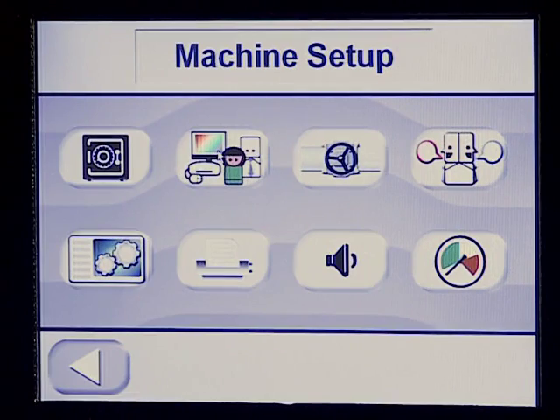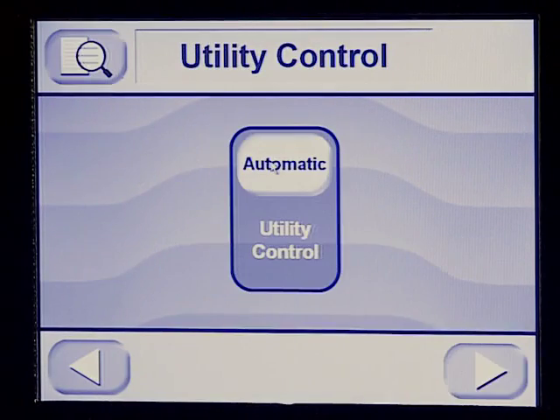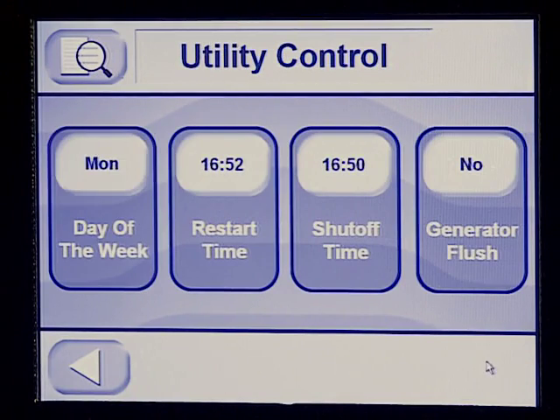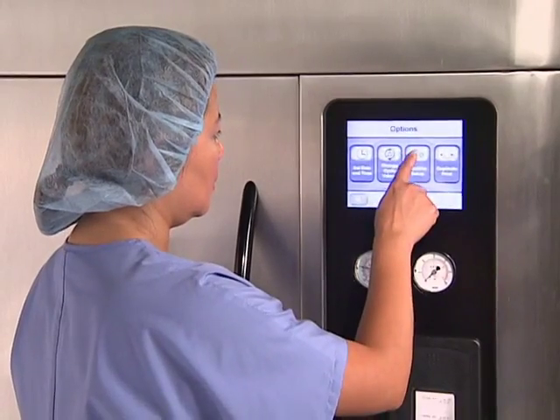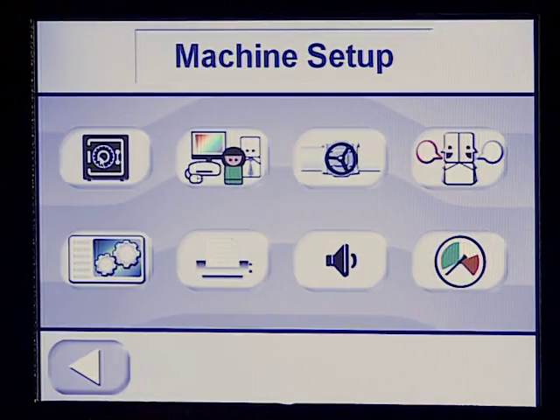You can also use the Auto Utility controls to program the sterilizer to automatically shut off its steam and water at the end of the day to conserve utilities. Shutdown and power up times can be programmed for any time of the day, on weekdays or the weekend. To set up this function, press the Machine Setup button on the Options screen. Press the Utility Control button.